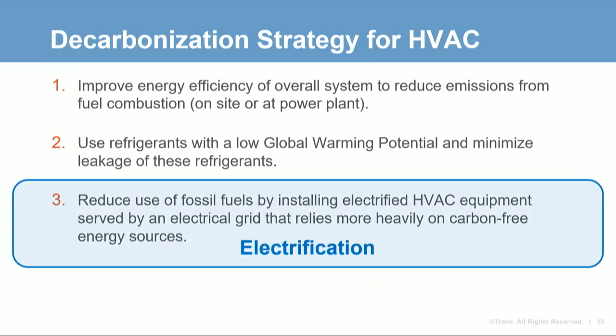The third strategy, electrification, can present a challenge when a building requires heating. Air source heat pumps are a common solution for electrified heating, but their capacity and efficiency degrade as it gets colder outside and they tend to be relatively expensive. Exhaust air energy recovery can be especially valuable when designing a building for electrified heating because it reduces the load on these heat pumps, allowing them to be downsized. For example, a sensible recovery device reduced the ventilation heating load by 50%, while a total recovery device reduced it by 70%.